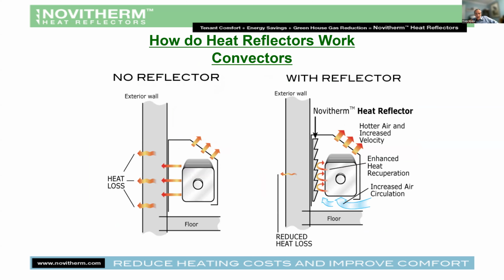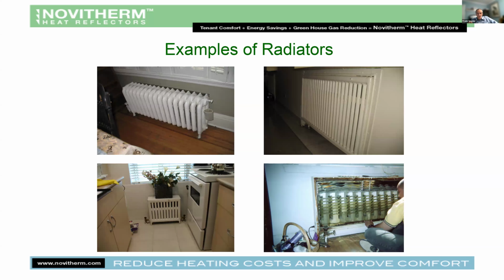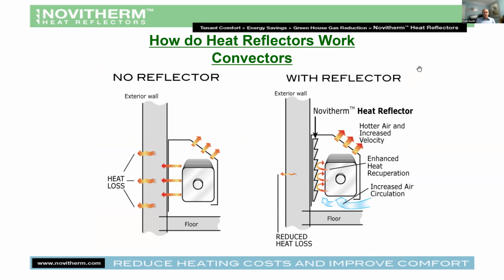So rads come in a variety of sizes. The convectors, in the next slide, come in a variety of sizes too. The concept works the same. You've got a heating unit, a poorly insulated exterior wall, and a disproportionate heat loss. So we put more heat gain into the room, as is evidenced by the affordable housing with Enbridge and the commercial. Once the reflectors are in, you turn down your boiler 10 degrees. Some can do more than that.